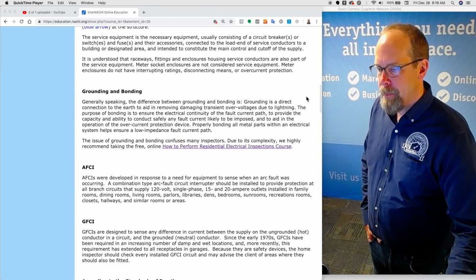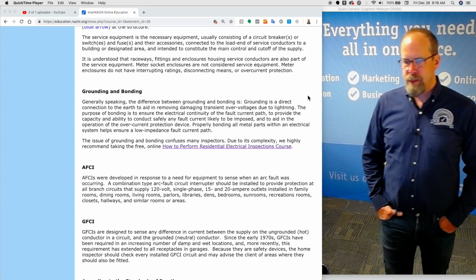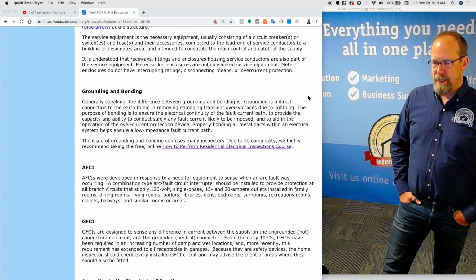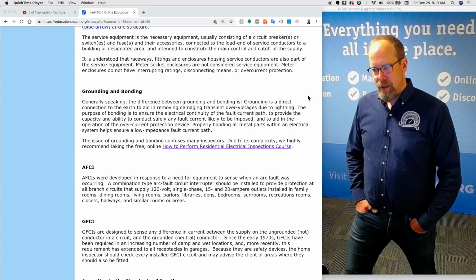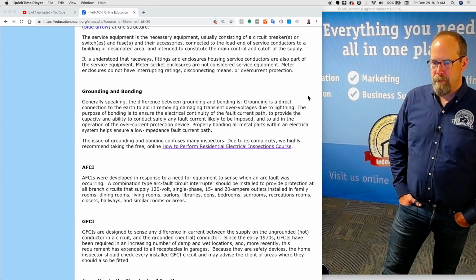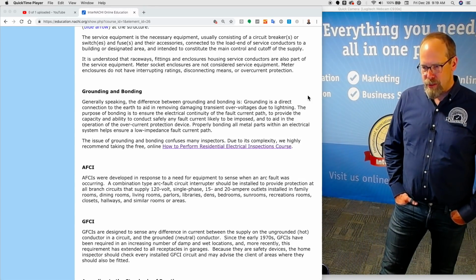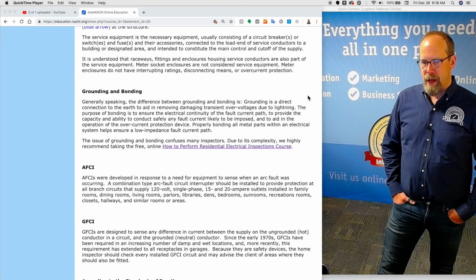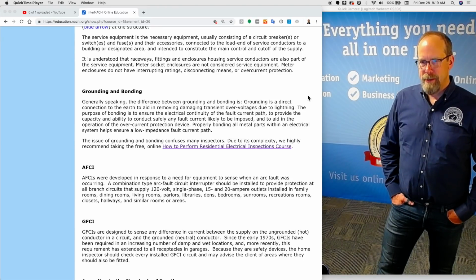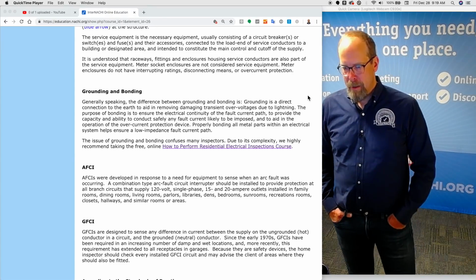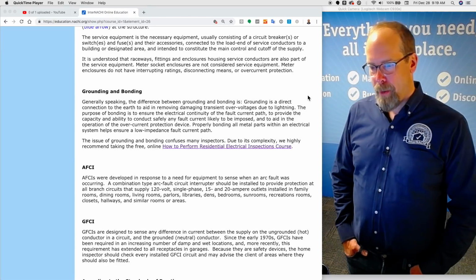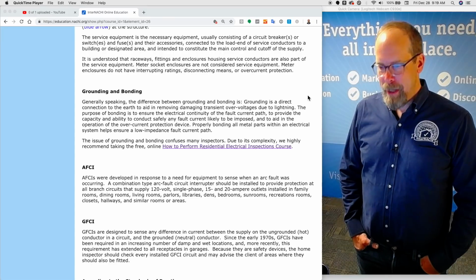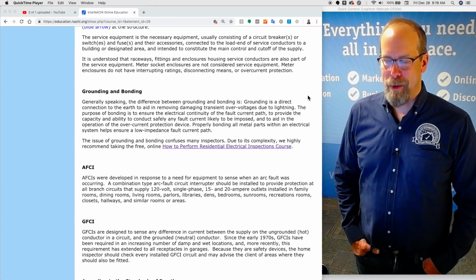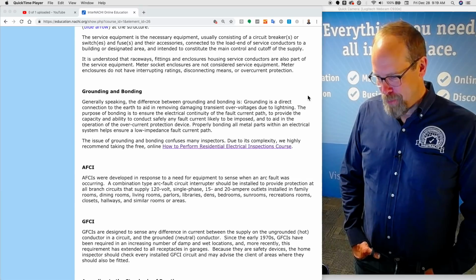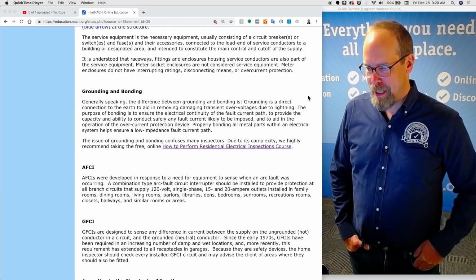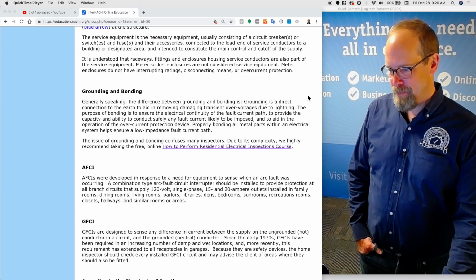Let's scroll up a little bit. Consisting of circuit breakers, switches, fuses, and their accessories, connected to the load end of service conductors to a building or designated area. And they're intended to constitute the main control and cutoff of the supply. It is understood that raceways, fittings, and enclosures housing service conductors are also part of the service equipment. Now, the meter socket enclosures are not considered service equipment. The meter enclosures don't have any interrupting ratings or disconnecting means or overcurrent protection.